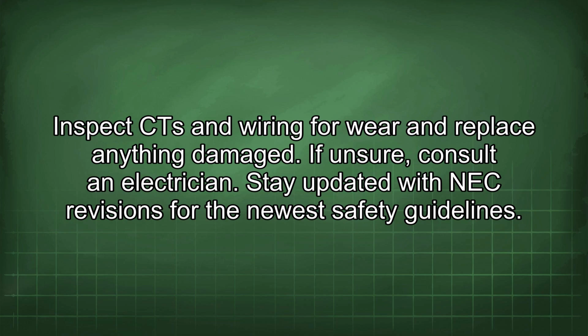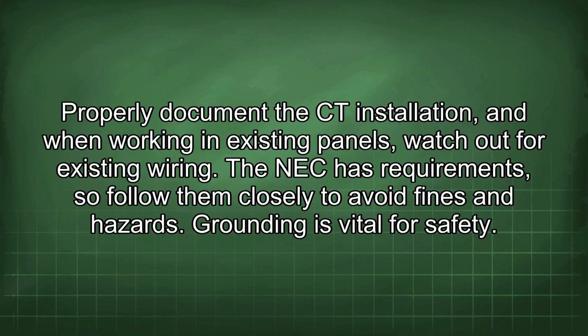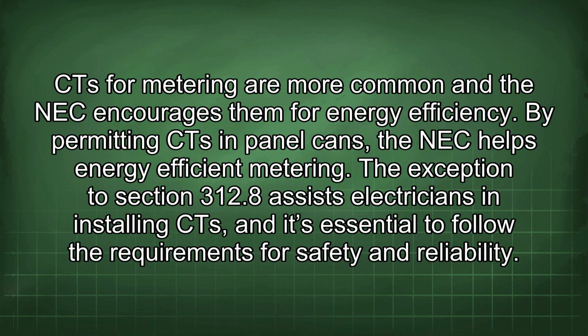If unsure, consult an electrician. Stay updated with NEC revisions for the newest safety guidelines. Properly document the CT installation, and when working in existing panels, watch out for existing wiring. The NEC has requirements, so follow them closely to avoid fines and hazards. Grounding is vital for safety. CT for metering are more common, and the NEC encourages them for energy efficiency. By permitting CT in panel cans, the NEC helps energy-efficient metering. The exception to Section 312.8 assists electricians in installing CT, and it's essential to follow the requirements for safety and reliability.